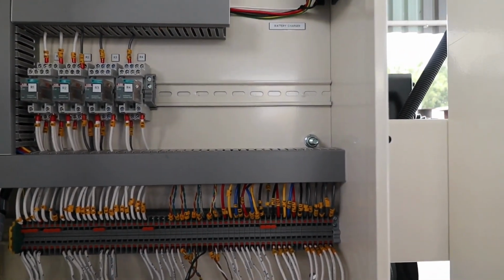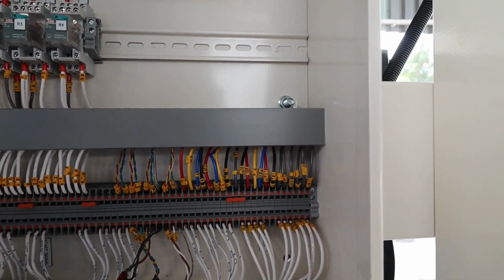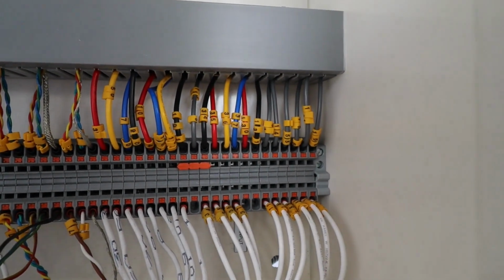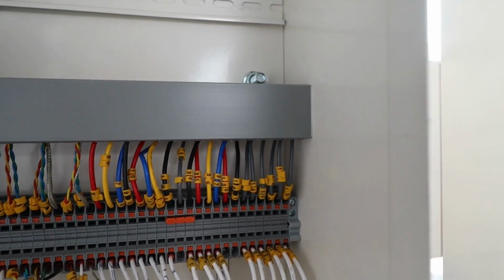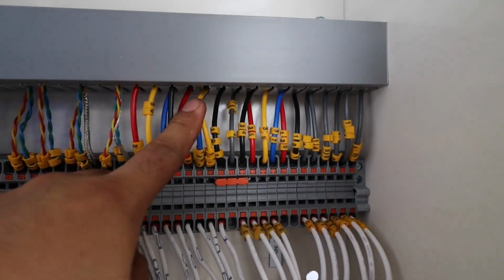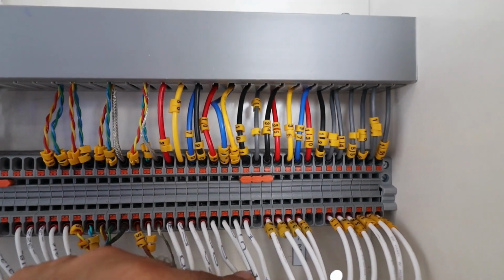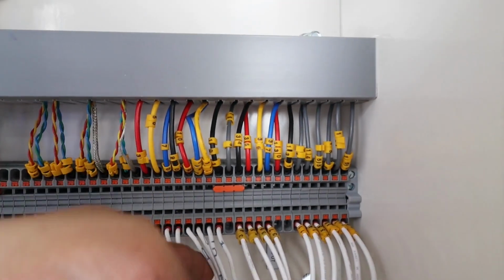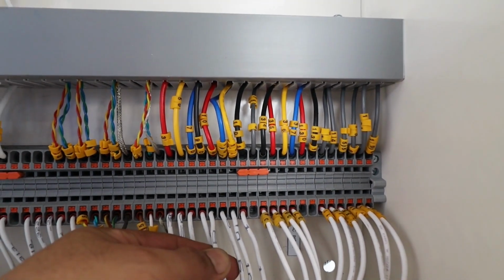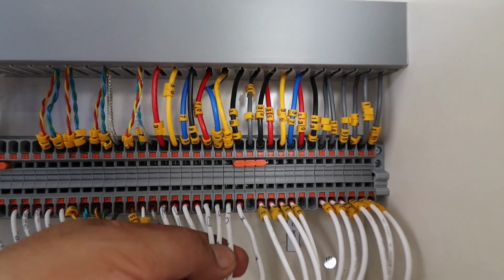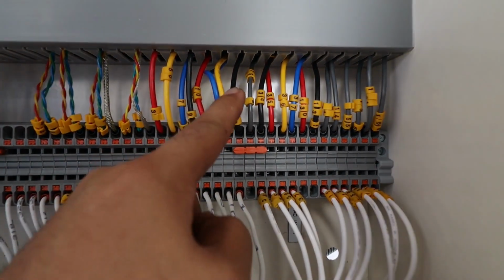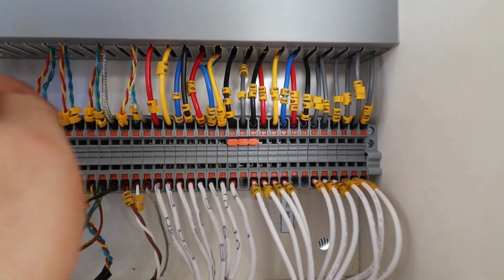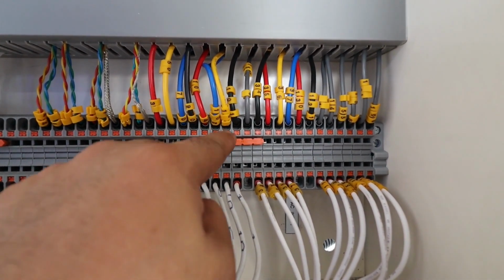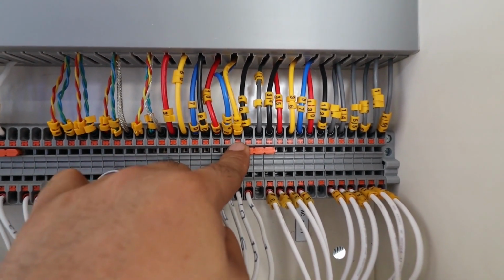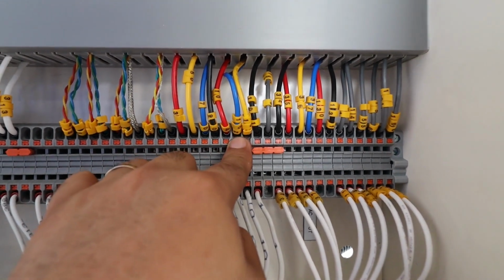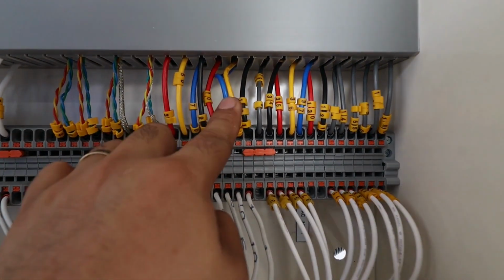So okay, we found out the problem is the P sequence. Here is the issue: the connection between our module sensing, which I already showed. This is the connection from our module's sensing voltage, and down here is from our breaker. From here we have terminals 8, 9, 10 - 8 is line 1, 9 is line 2, 10 is line 3. From the color coding above, it is wrong, which is why the module detects wrong connections. So the P sequence is also wrong, and the rotation of your generator will be understood as wrong, causing it to shut down on P sequence.